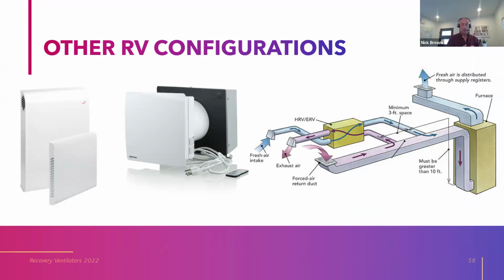The two on the left do the recovery in the box, and they do inlet and outlet right there through the wall. So there might be a little bit of mixing on a windy day, but generally they're proven to work. The one in the middle has a ceramic core. It's installed in pairs, and they reverse direction of the airflow. Pretty cool. So they temper the ceramic core by blowing out, and then they switch air direction, and now the incoming air runs through that tempered core, and then every minute or so they alternate. I thought that was pretty cool.